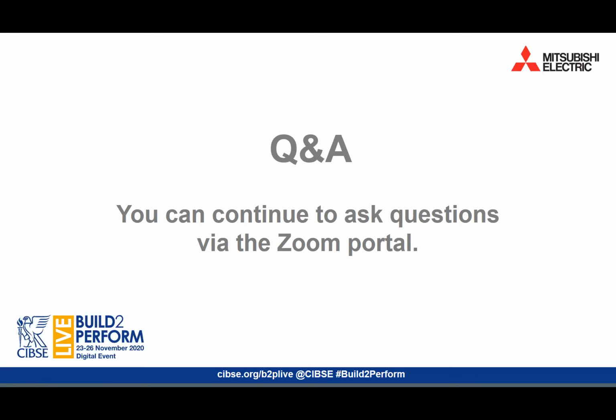So we have one question from a nameless attendee, but they've asked if this product can be used for heating or just hot water. In fact, the best application for this technology is sanitary hot water. As we walked through with the explanation of the need to have high delta T's and low inlet temperatures, that suits an application of almost semi-instantaneous hot water production.